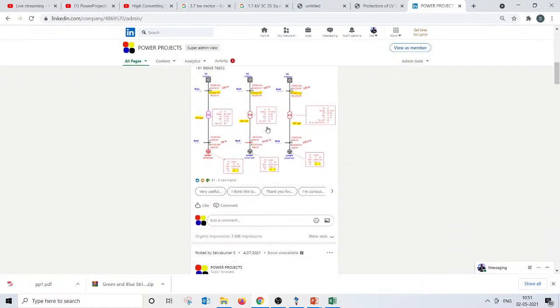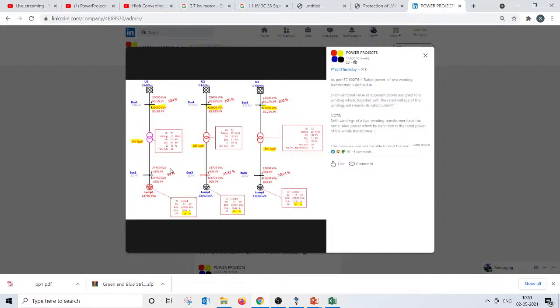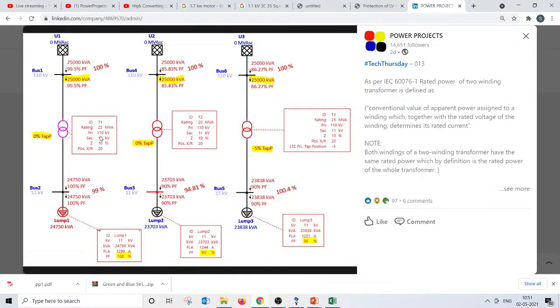Though we call the capability curve of a transformer a circle, we have put up the case of 100% loading of the transformer purely by real power, purely by reactive power, and with reactive power but with an on-load tap changer. How much real power you can load and how much reactive power you can load is specified here. I can zoom in on the image a little more. Yeah, this is 25 MVA, not 2.5 MVA anyway. So for a 25 MVA transformer, you can go up to 24.75 MVA at unity power factor, but only up to 23.73 MVA if the power factor is 0.9, right?